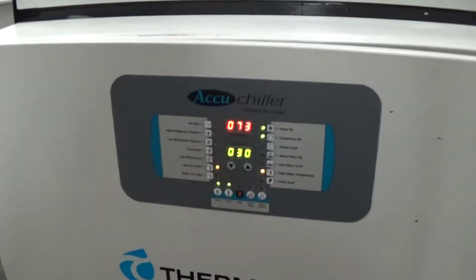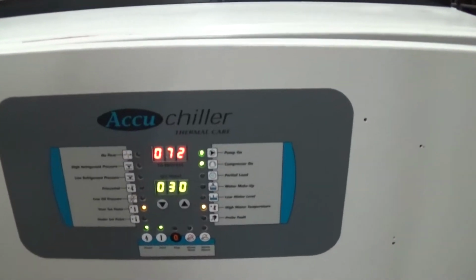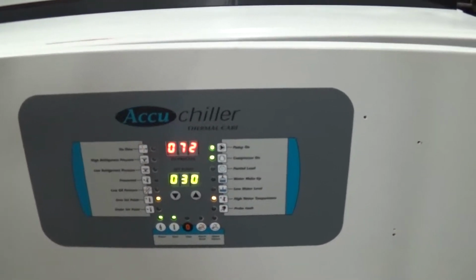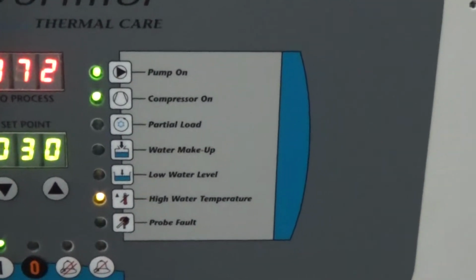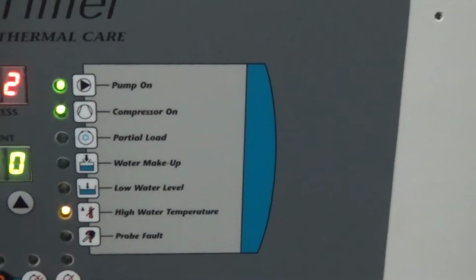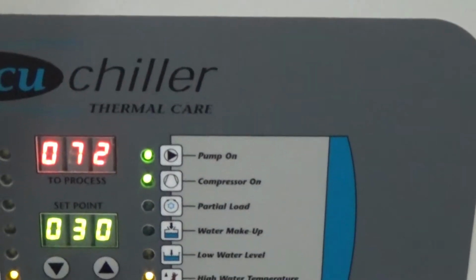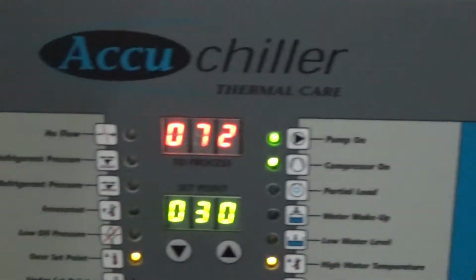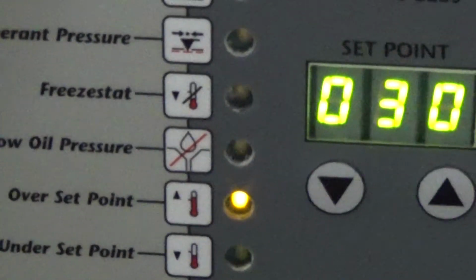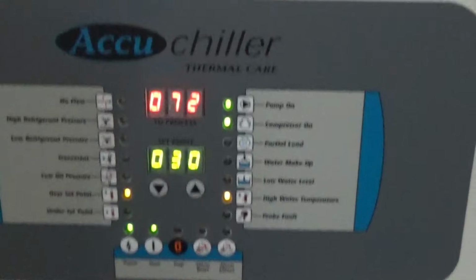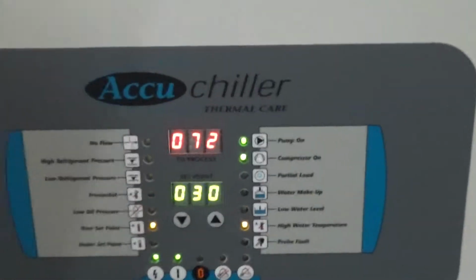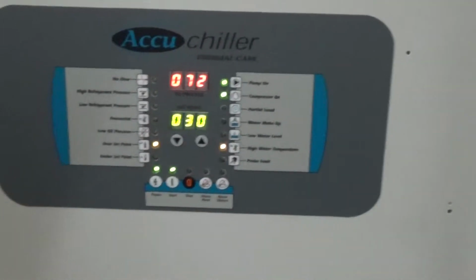Because we're at such a high temperature with respect to our set point, you'll see that high water temperature light on, compressor light on, pump on, and over set point. Okay. Now, we're just cooling down to 30 to show how well this cools.